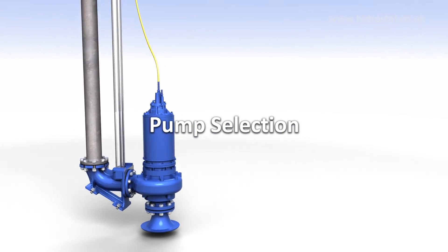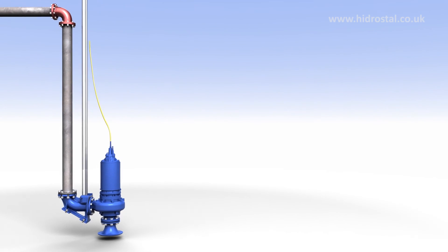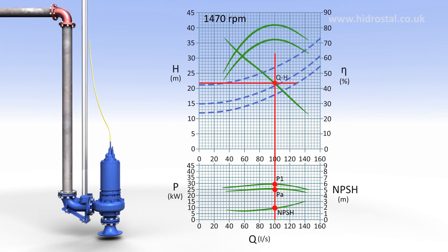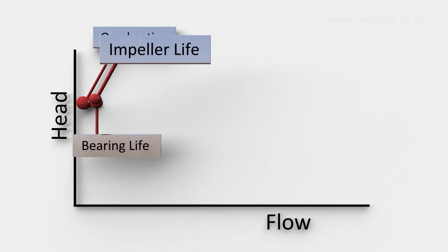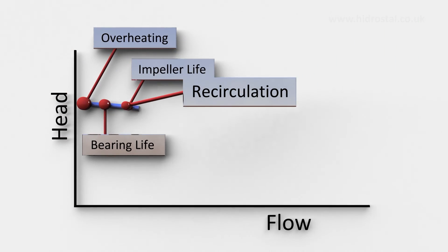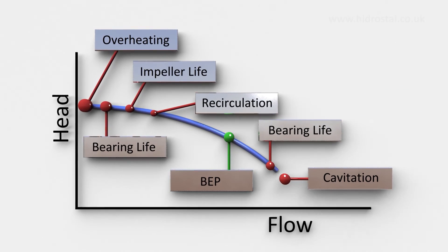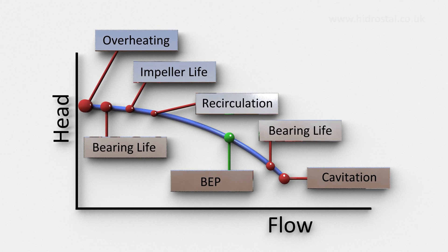Good pump selection can really boost a system's performance. Knowing and utilising the pump's best efficiency point is crucial. Ideally the highest utilisation duty point should occur between 80 and 105% of the pump's BEP. Anything outside this range can lead to increased operational and maintenance issues, increasing the cost of ownership for the end user.